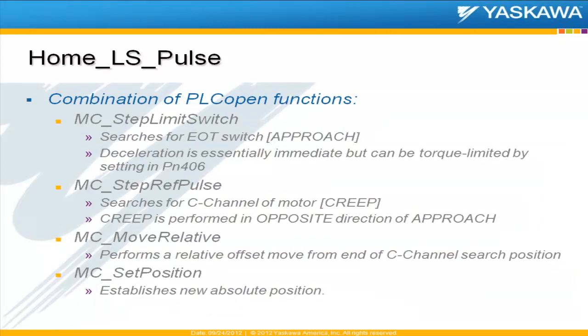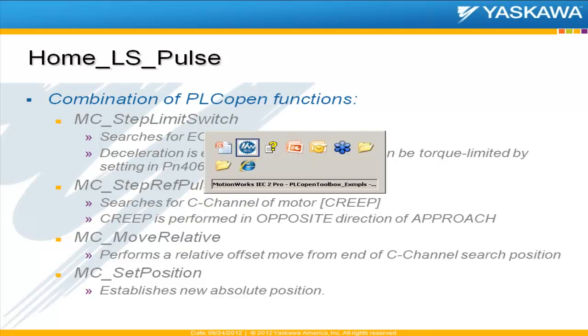Inside the function block, it's really a combination of PLC open functions in a sequence. First, it uses an MC Step Limit Switch to go find the limit, and the deceleration is essentially immediate, but it can be torque-limited if needed by setting a value in parameter 406. Then it moves on to an MC Step-Ref Pulse, which searches for the C channel — that's the creep part. The creep is always performed in the opposite direction of the approach. Then it does an MC Move Relative, and finally sets the position for the new absolute position.